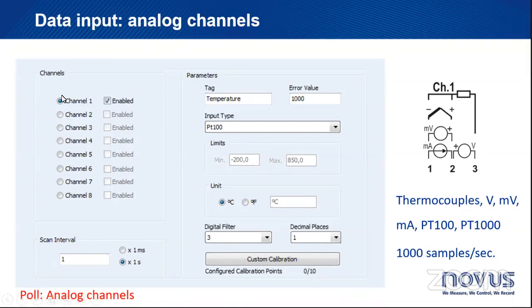We have the channels, so 8 channels that can be enabled or not. We have a scan interval that is configurable and it is shared between all those channels, okay? So you can read every second or every millisecond, it's up to you. And then the parameters. So here you select a tag, an error value, input type, I'll go through all of them, right? Input type, unit, digital filter, decimal places, and custom calibration. So what do all those parameters mean?